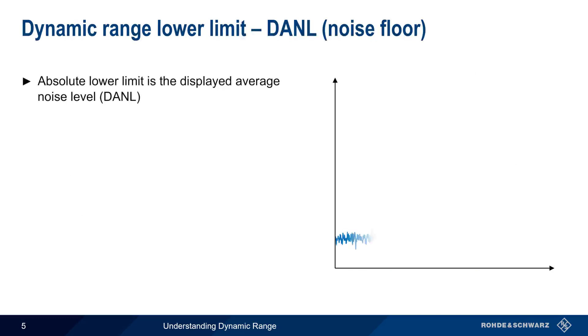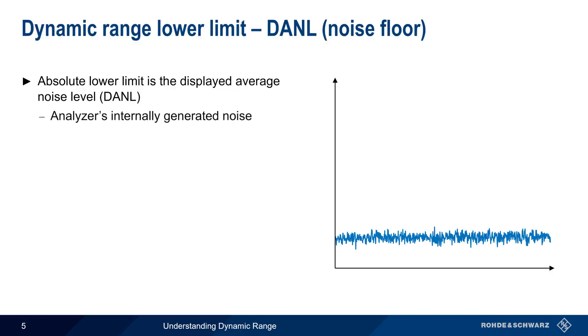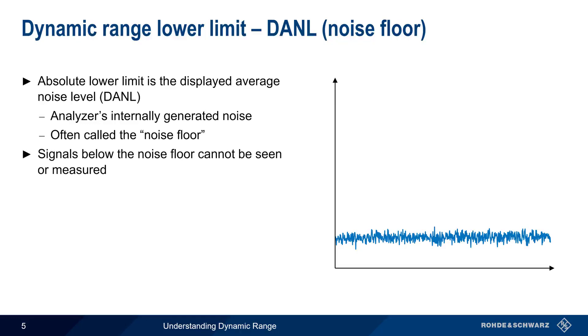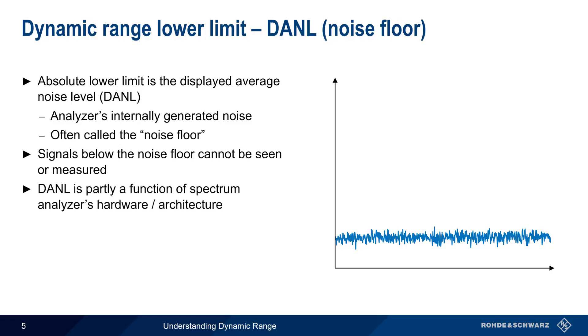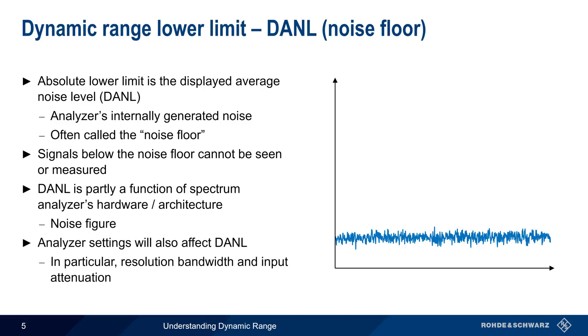The absolute lower limit of dynamic range is the analyzer's displayed average noise level, or DANL. This is the noise generated within the analyzer itself and is often referred to as the analyzer's noise floor. DANL limits dynamic range since signals with amplitudes below this noise floor cannot be seen or measured. An analyzer's DANL is partly a function of the spectrum analyzer's hardware and architecture, often quantified in terms of the analyzer's noise figure — that is, the amount of internal noise that the analyzer adds to the input signal. But DANL is also a function of the analyzer's user-configurable settings. In particular, lowering either resolution bandwidth and/or input attenuation will decrease an analyzer's DANL, and thus usually improve dynamic range. Please see the separate presentations on noise figure and DANL if you'd like to learn more about these two topics.